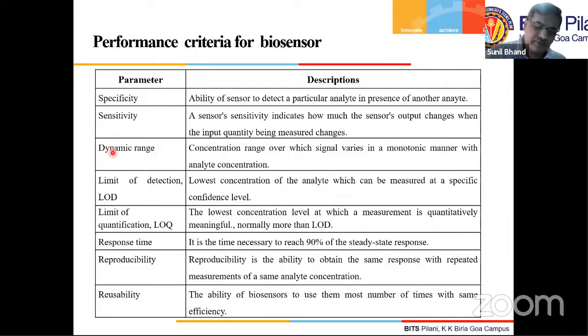Likewise, many times, as you see in the case of blood glucose, you need about 80 milligram per deciliter. That's the limit for blood glucose. So if your sensor cannot measure 80, and can measure only 40, then your sensor is not fit, your dynamic range is not sufficient. So you should be able to go up to 400 or 500 milligram per deciliter of glucose. So your sensor should meet the dynamic range requirements.